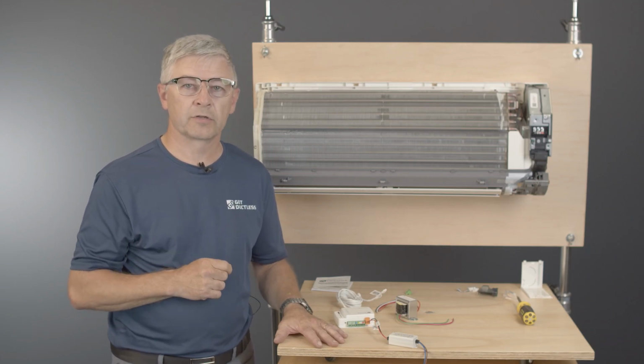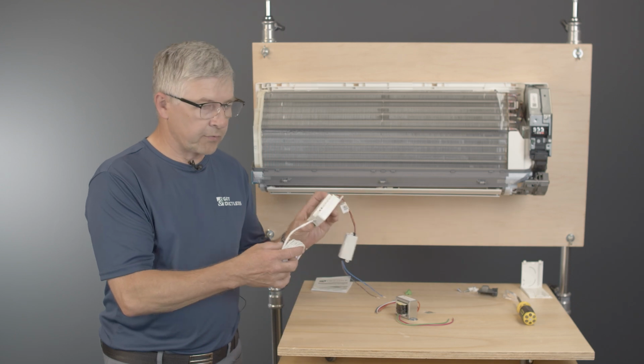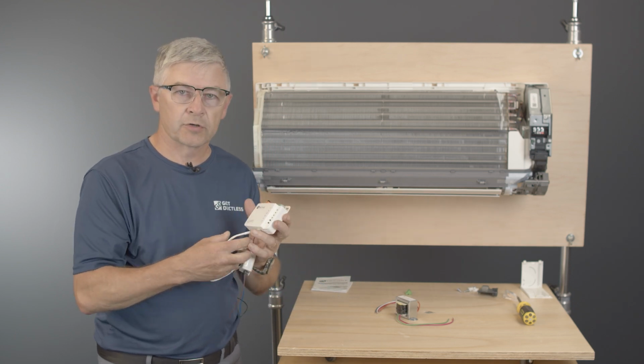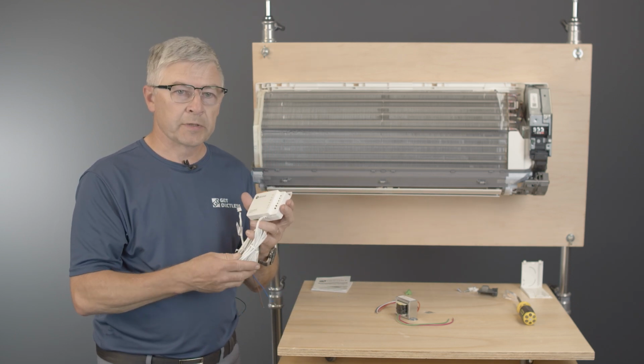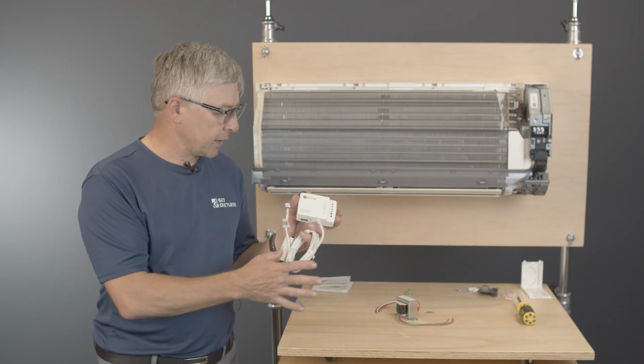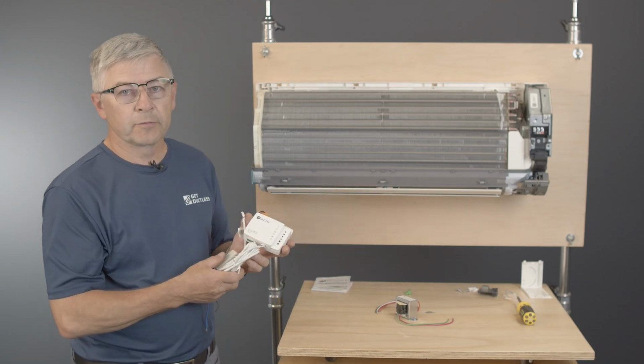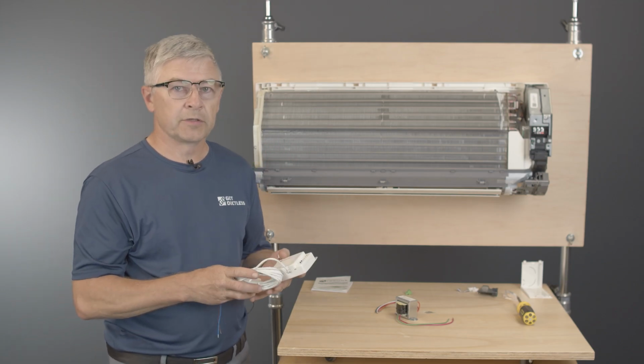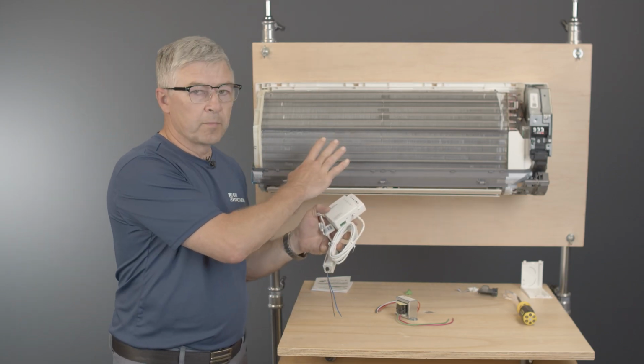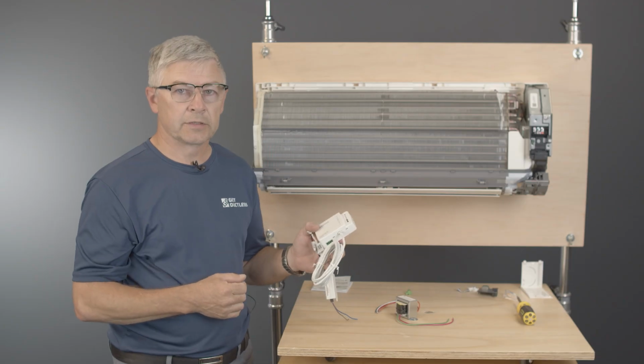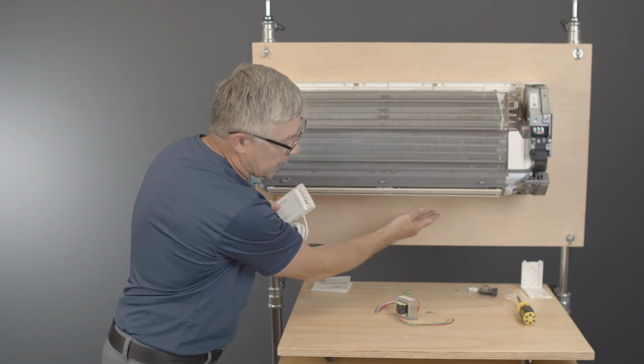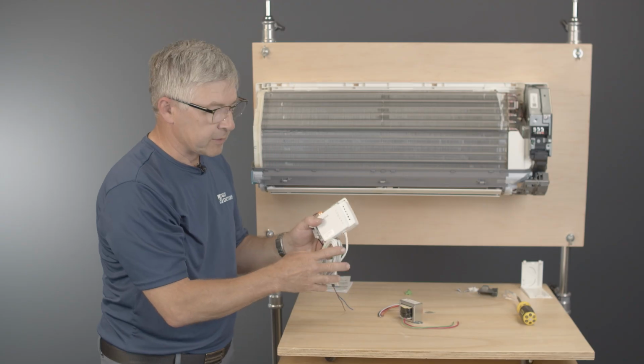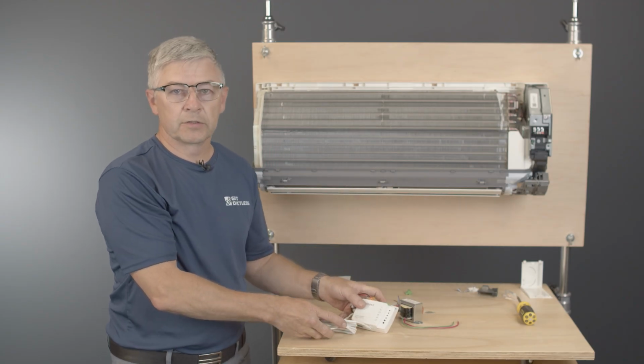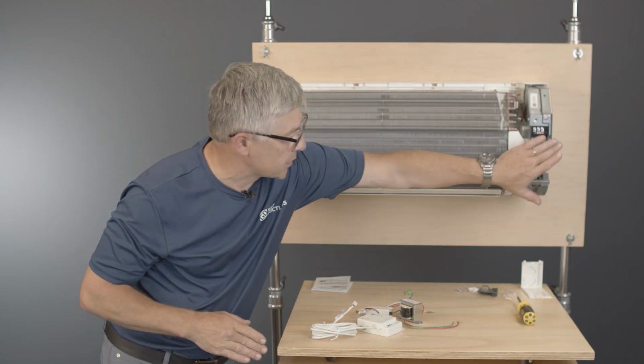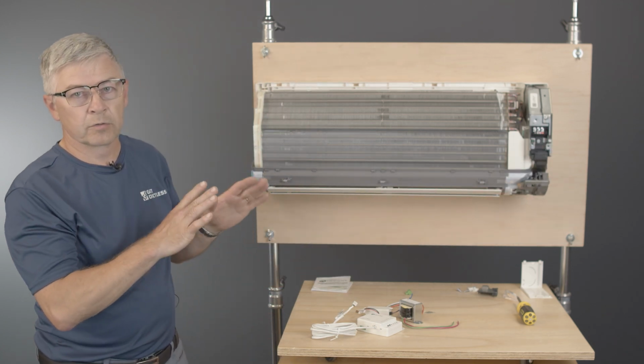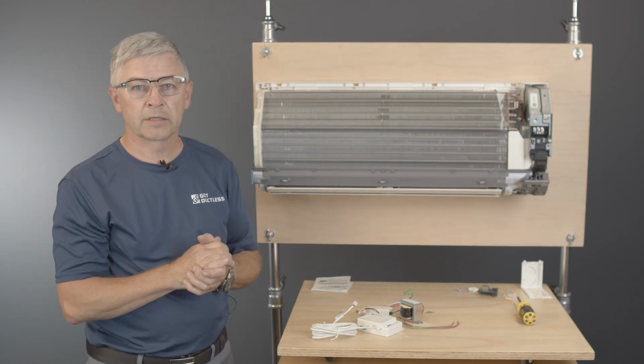It's very easy to install this on air handlers such as horizontal ducted or multi-position. There's plenty of room to hide this adapter and all the transformers inside. Now you have to be really creative, or your install technician has to be very creative, to do this for wall-mounted, floor-mounted, or ceiling cassette units. There's not much space to hide all these wires and adapters inside the unit. So most likely you'll need to use some sort of access panel installed somewhere around the unit to make sure it's all looking good, working properly, and easily accessible if necessary.